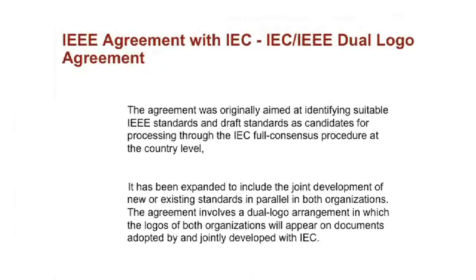First, it was aimed at identifying IEEE standards and draft standards as candidates for processing through the IEC full consensus procedure. Then it was expanded to include joint development of new and existing standards. So at the beginning we sat down and said, you guys in IEEE have standards we don't cover at all in IEC. The example I gave before was the generator circuit breaker standard, which in IEEE has 15 years of history as C37.013. This covers generator circuit breakers, a very specific application, and IEC doesn't have anything equivalent. So I said, could you just adopt this as an IEC standard, as long as it goes through the IEC full consensus procedure?